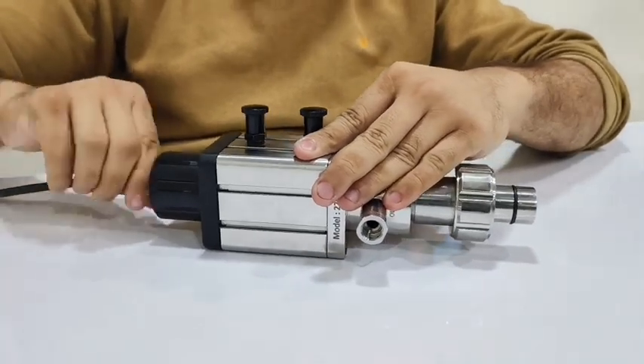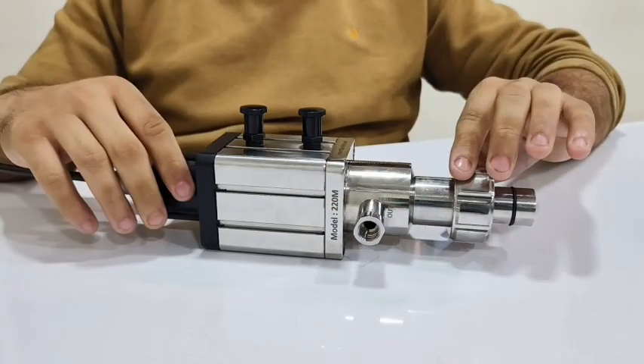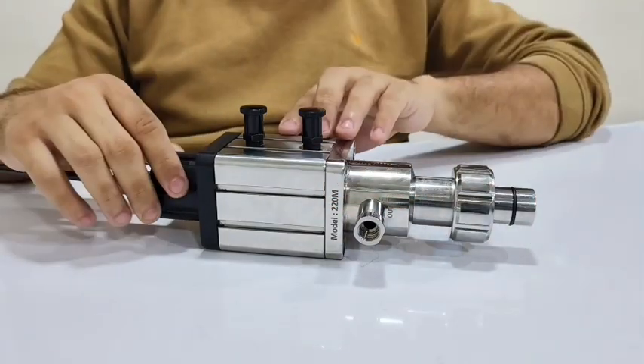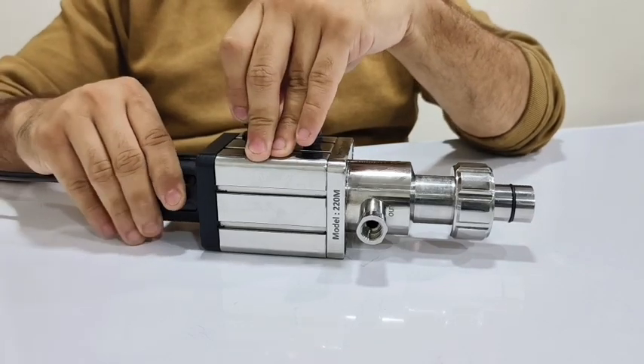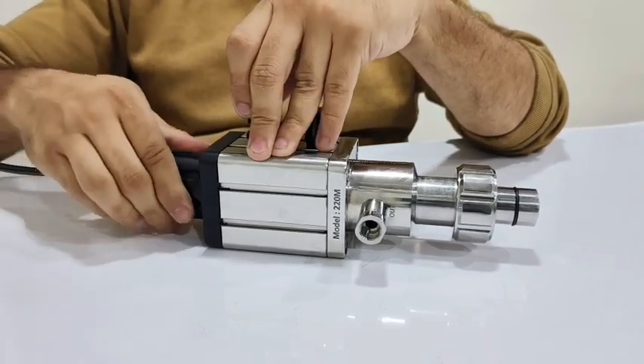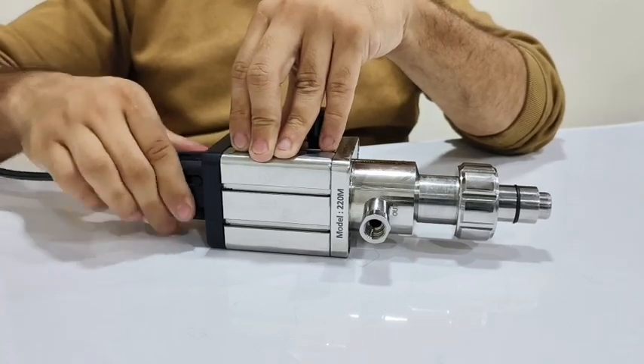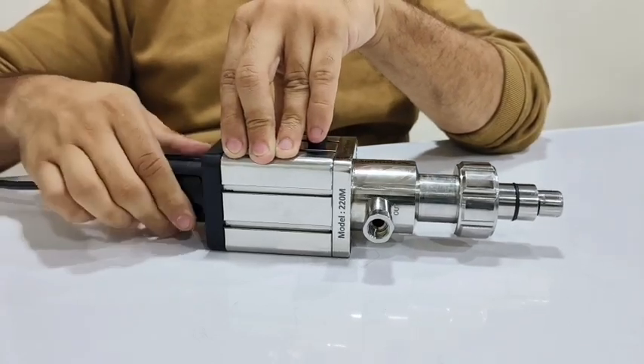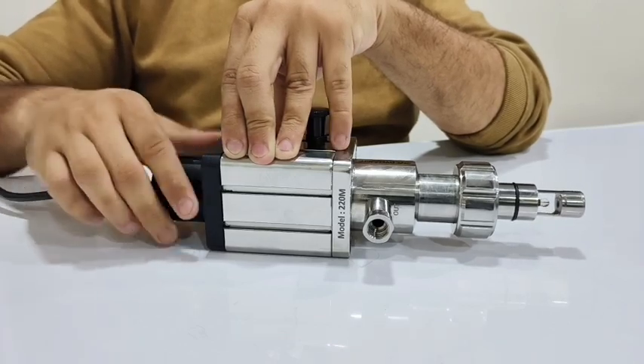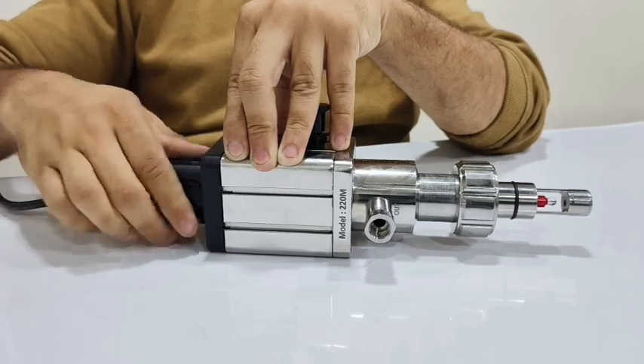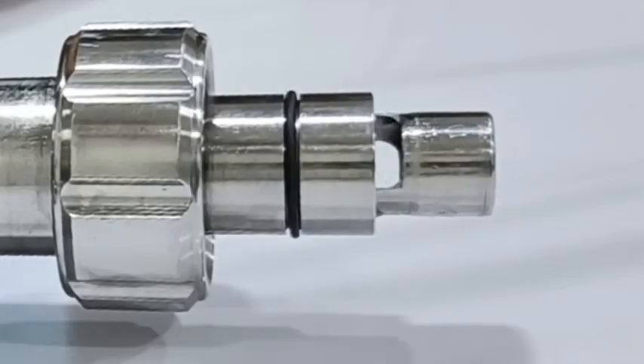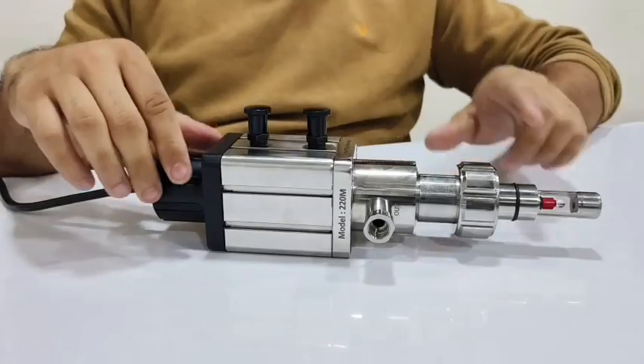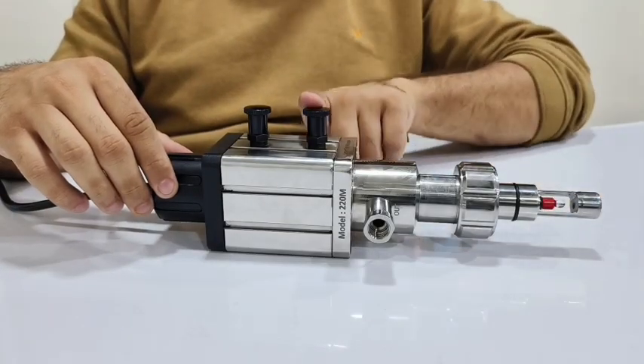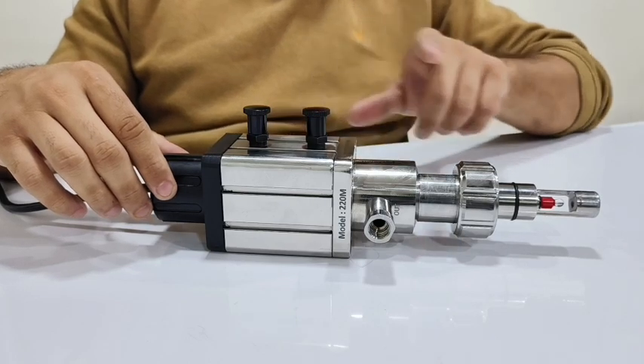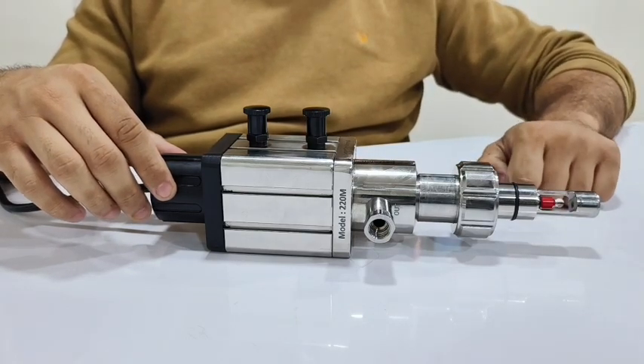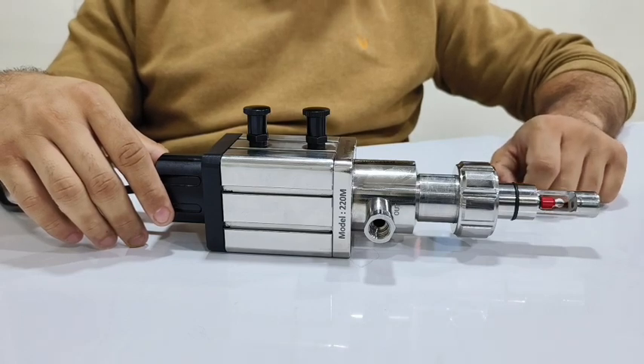Once the electrode is inside, the system is now ready to use. When you want to do the measurement, you have to just unlatch this locking pin and rotate the rotary nut in a counterclockwise position so that the retractable assembly will be inserted with a 40 mm stroke length. The electrode will be locked in the measurement position through this latch.